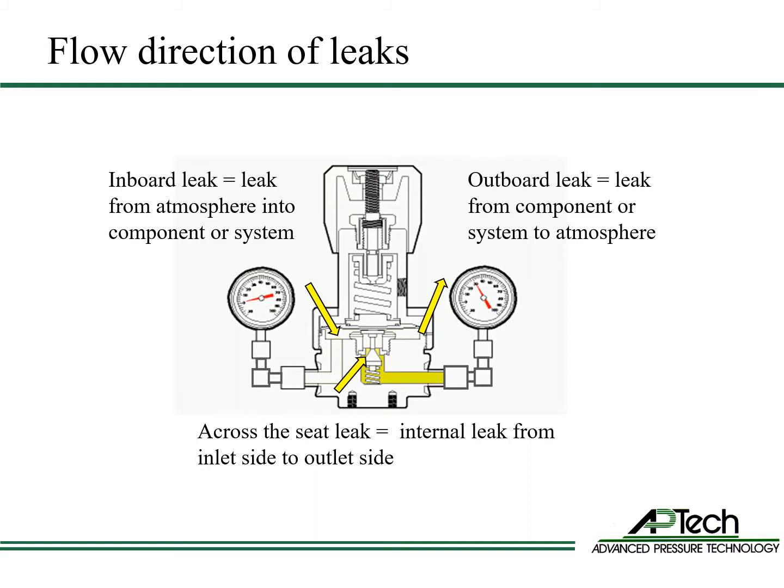There are three leak flow directions that are tested in valves and regulators. An inboard leak is simply a leak from atmosphere into the internal volume. An outboard leak is a leak from the internal volume to atmosphere. A leak across the seat is an internal leak across the seat from the inlet to the outlet side. Inboard, outboard, and across-the-seat leaks are tested to ensure leak-tight operation.